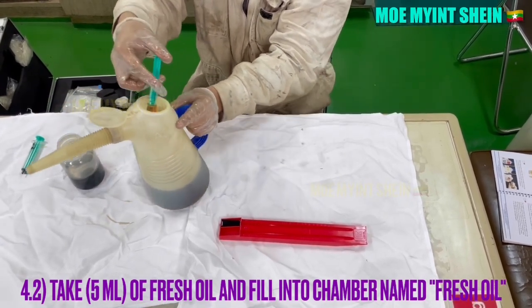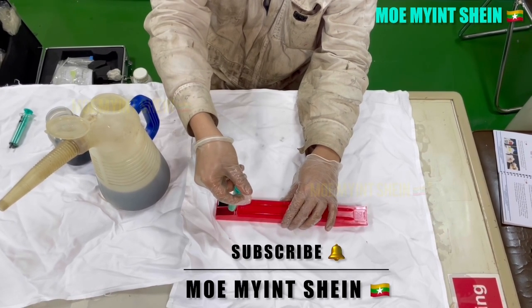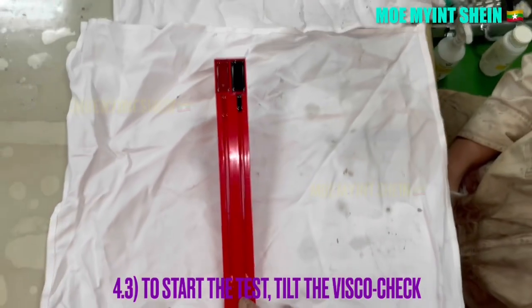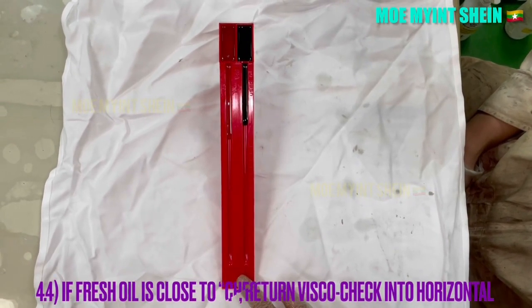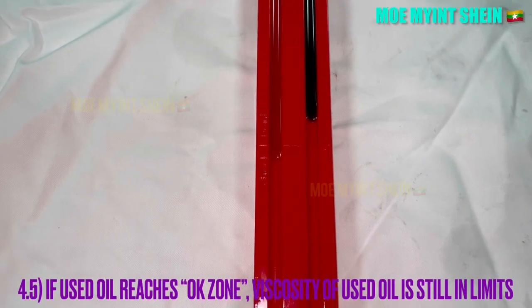And then, take 5 milliliters of fresh oil and fill into the chamber named fresh oil. Tilt the Visco-Check and start the test. Return the Visco-Check into horizontal position when the fresh oil closes to the check point. If the used oil reaches the OK zone, the viscosity of the used oil is still within limits and can be safely used. If it does not reach the OK zone, the used oil should not be used and you should plan to renew it.